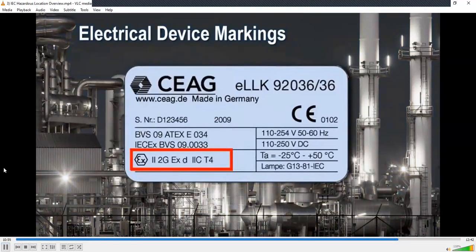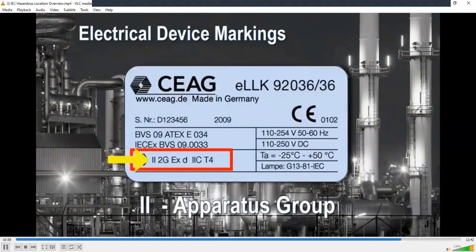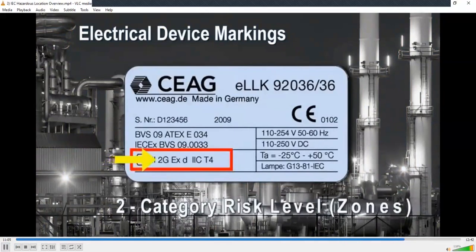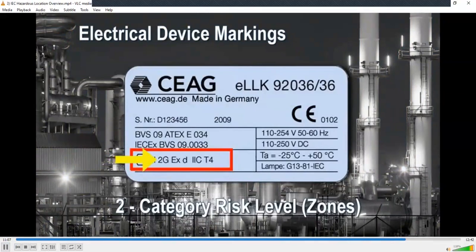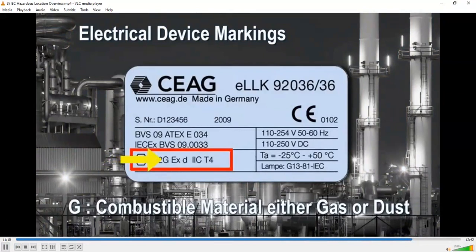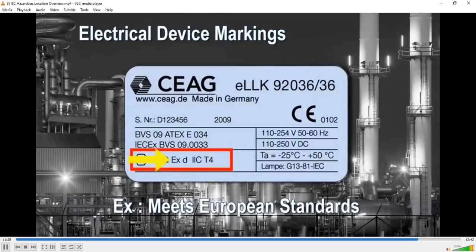The first identifying mark will reflect the apparatus group by hazardous application. A 1 would indicate usage for coal mines, while a 2 would indicate general industrial environments. The next identified mark is the category risk level. As mentioned earlier, there are 3 category risk levels that would identify the occurrence of an explosive combustible material. The next mark identifies the type of combustible material within this hazardous environment. The available options would be the letter G for gases or the letter D for dusts. The next mark identifies this fixture as manufactured to meet the European standards.